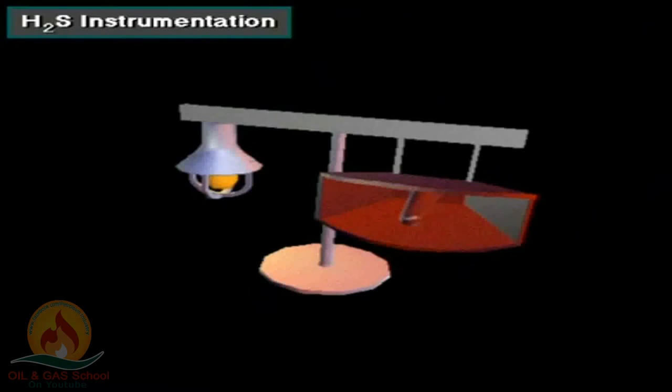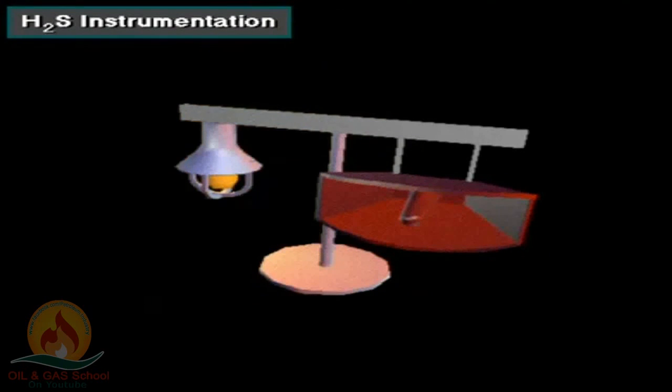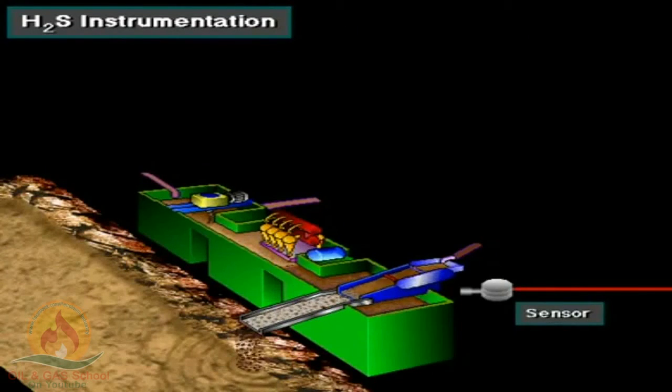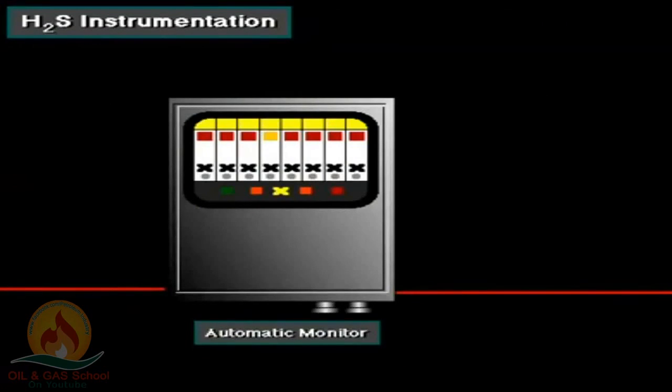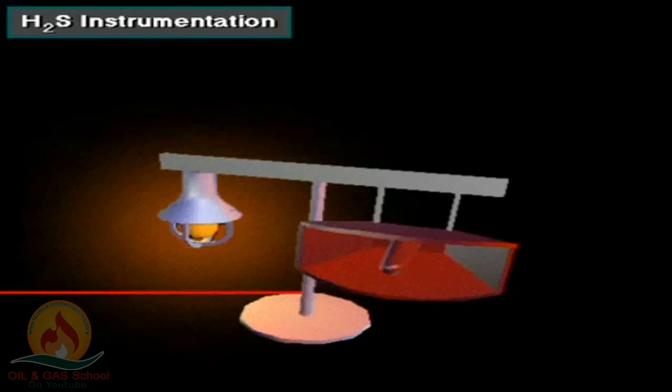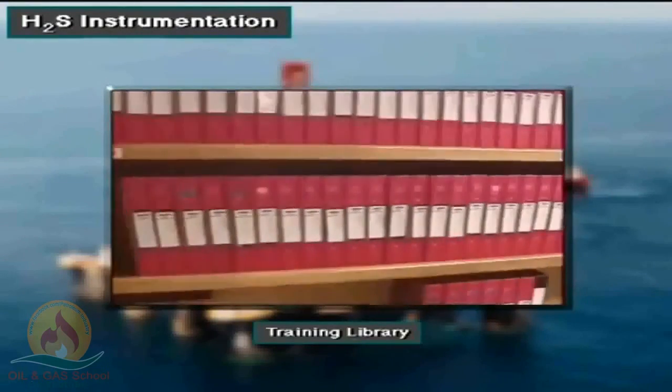This is an audible and visual H2S alarm. The horn sounds a siren while the light flashes brightly if activated by H2S sensors placed on the rig. H2S sensors may be placed near the mud tanks, at the bell nipple on the rig floor, shale shakers, flowline, rig accommodations air intake, and other places. When a sensor picks up H2S gas above a predetermined level, the monitor triggers both visual and audible alarms. Upon hearing or seeing the alarm, crew members can take action to avoid injury or death. You will receive detailed H2S training if your rig is working in an area where H2S may be encountered.